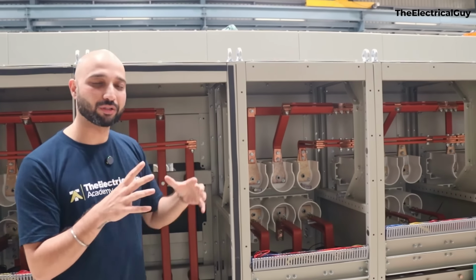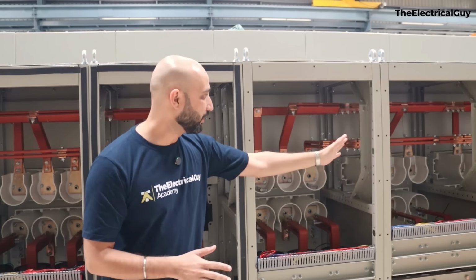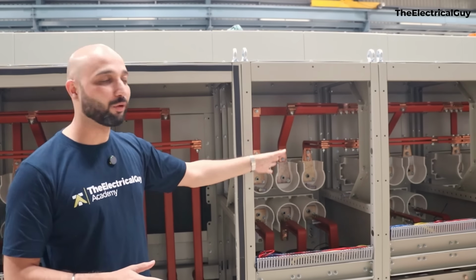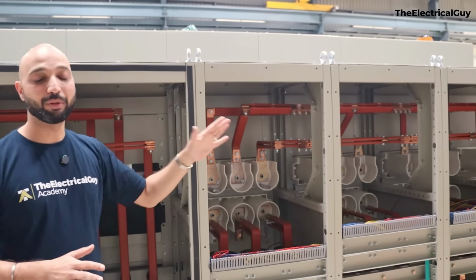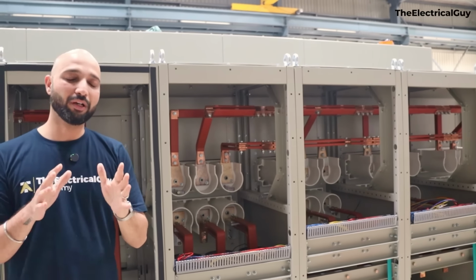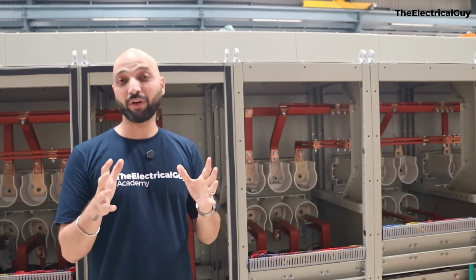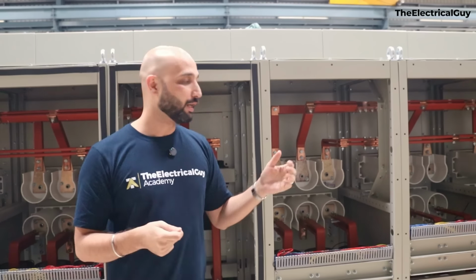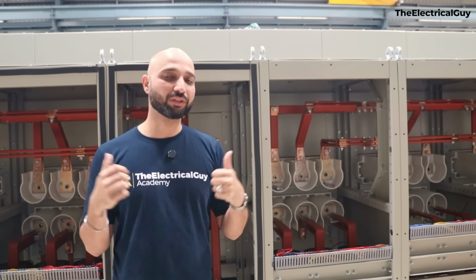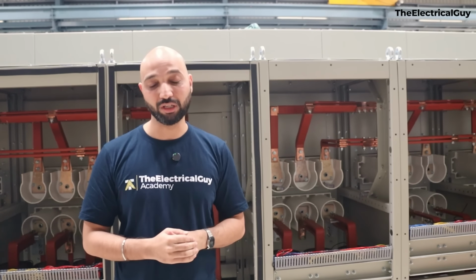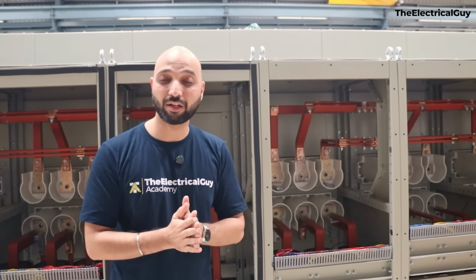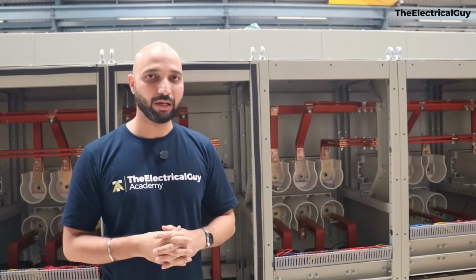So only when we close that, the current will flow. And you can see if you close this circuit breaker when both of the incomer circuit breakers are in closed condition, we will definitely have a short circuit. So to avoid that, we put interlocks in the system. You won't be able to close a bus coupler breaker when both of the incomer circuit breakers are in closed condition. There can be mechanical interlocks as well as electrical interlocks.